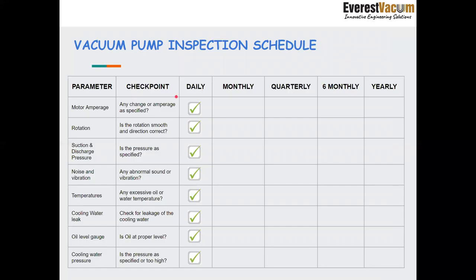So daily we need to check what is the current being drawn by the pump. Is it within limits? Is the rotation correct? Are the suction and discharge pressures within limits? Is there any abnormal noise? Temperatures, cooling water leakages, oil level gauge, all these need to be checked on a daily basis.